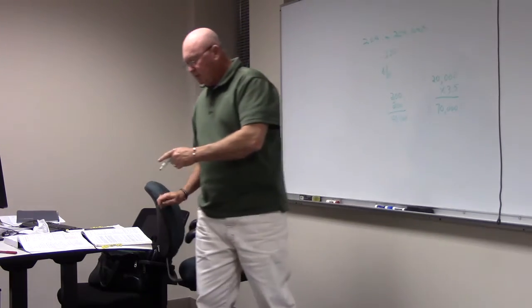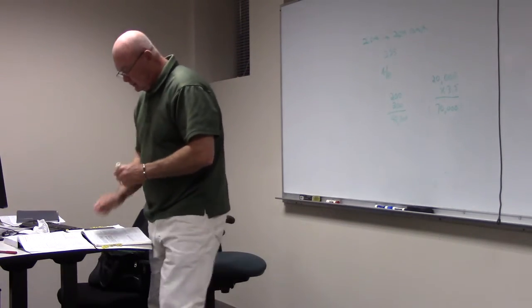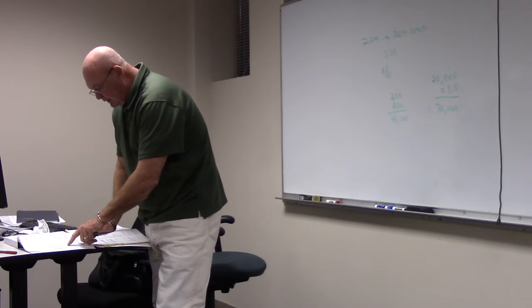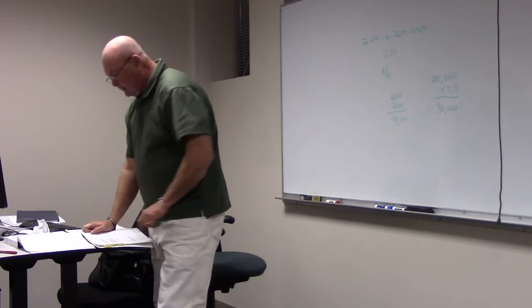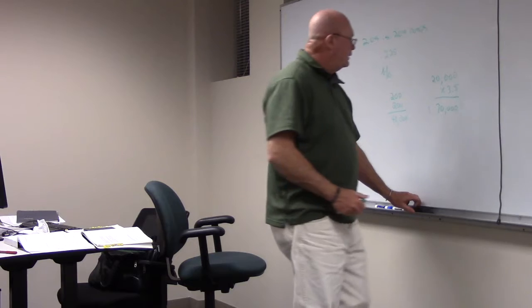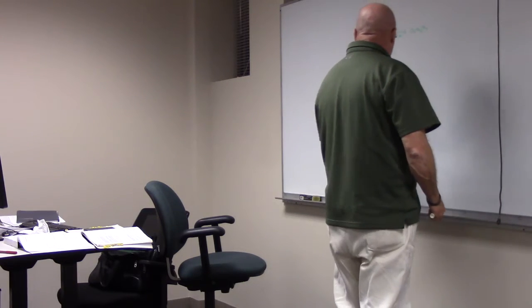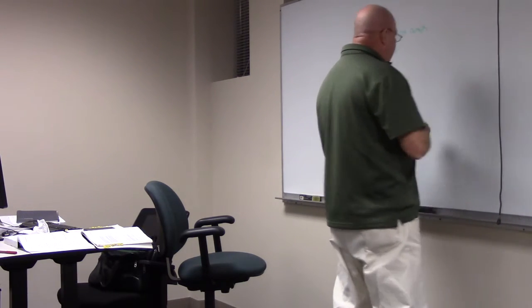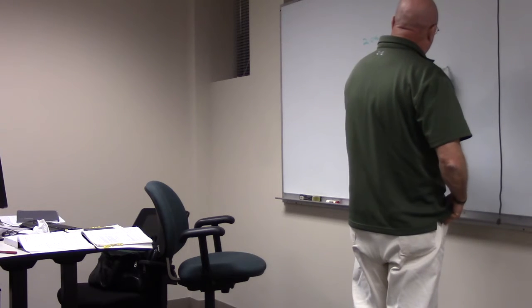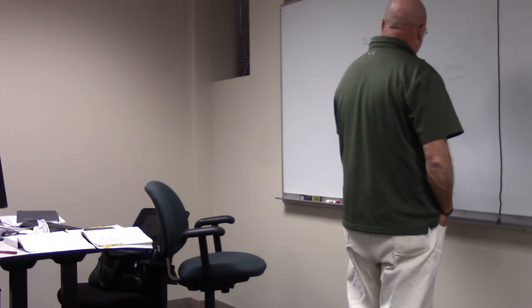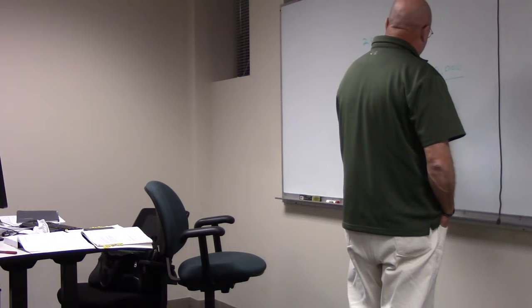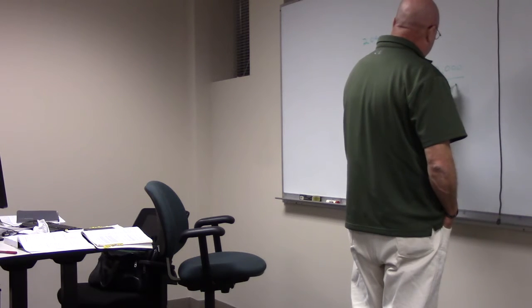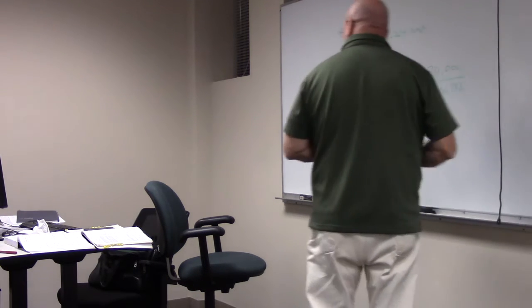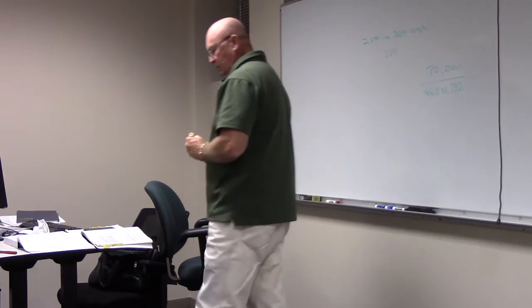This one here is larger. If you see in the book what it says to do, it says since the connected load is less than the NEC, it is neglected. So we have to use the 70,000. Now we get to the lighting load. So we have 70,000, and it's 480. Multiply that out and see how much that comes to.